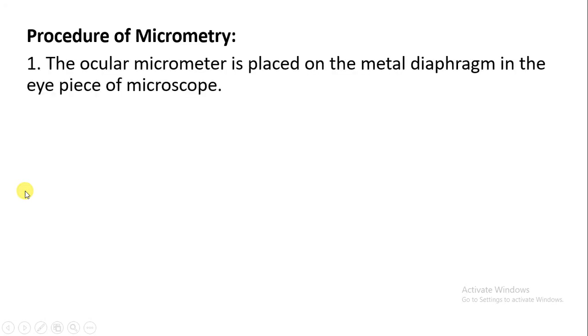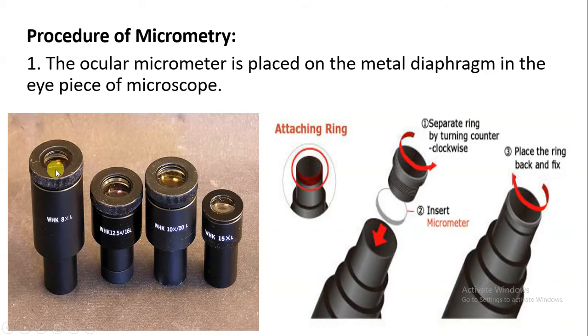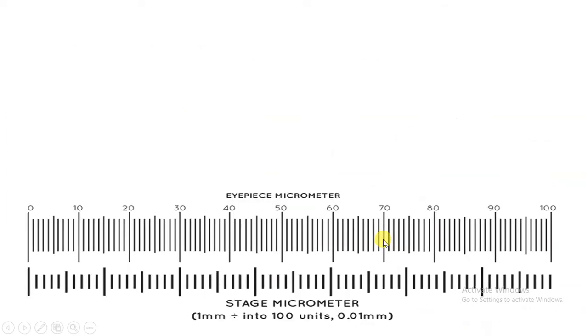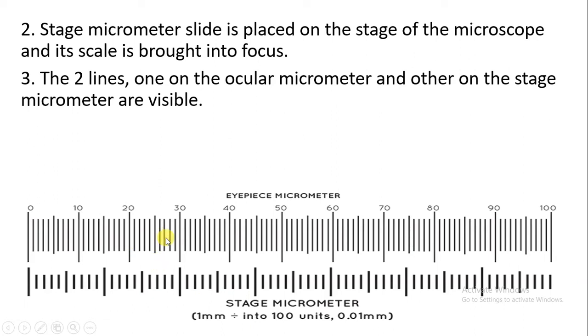Next, what is the procedure of micrometry? First of all, we do require the ocular micrometer. It is placed on the metal diaphragm in the eyepiece of the microscope. The eyepiece is opened, and the ocular micrometer is inserted. Then the opening is closed again, and in this way the scale is inserted and visible inside the eyepiece. Second step — the stage micrometer slide is placed on the stage of the microscope and the scale is brought into focus. Then the lines of the ocular micrometer and stage micrometer need to be coincided — both lines should be visible.